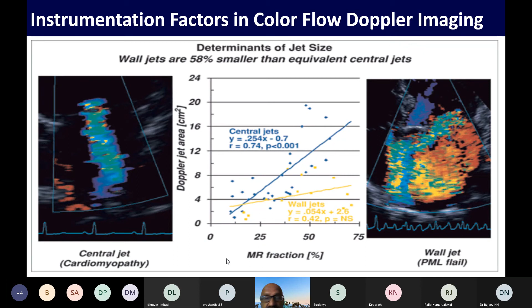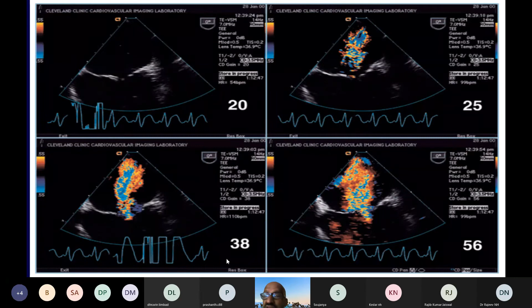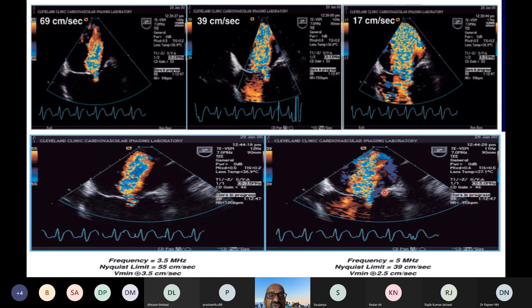This is very important, so that we are not measuring wrong color flow Doppler signals, unless you use the appropriate settings of the color gain and frequency settings on the machine. So the same mitral regurgitation can be visualized, indicating varying degrees of severity if the frequency settings are not kept optimal. Normally we keep it between 50 to 60 centimeters per second. That is the color flow setting.